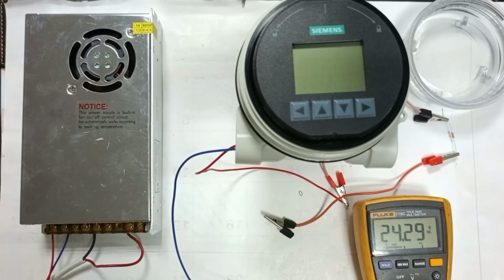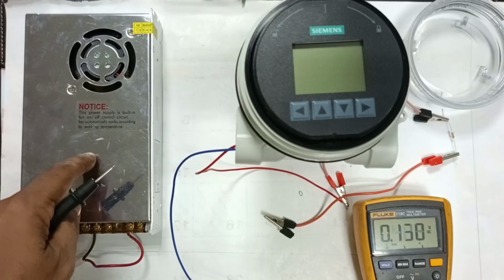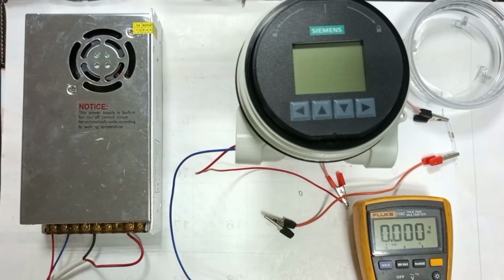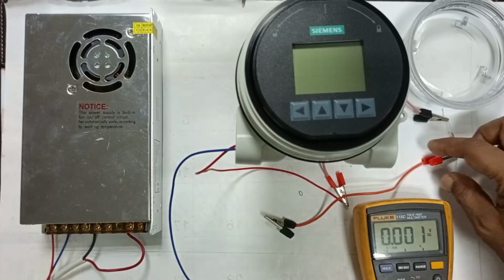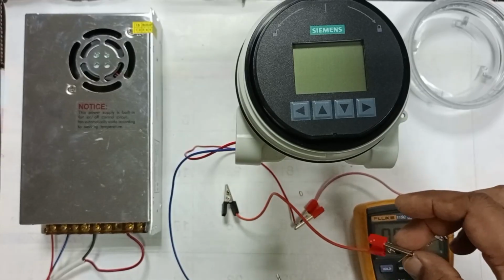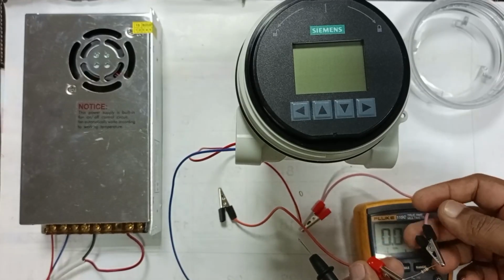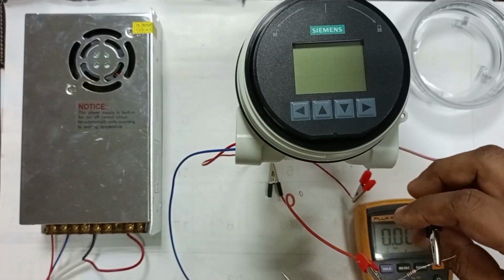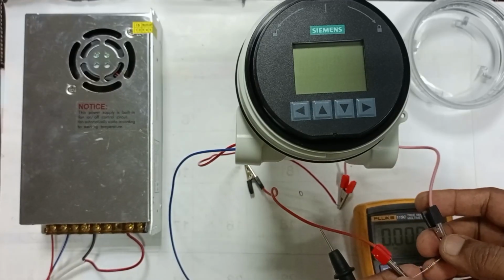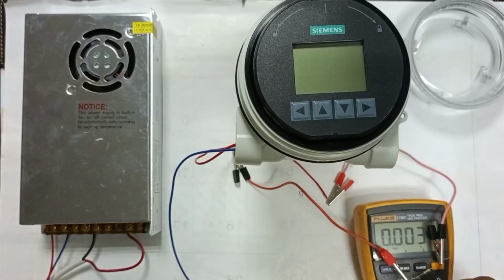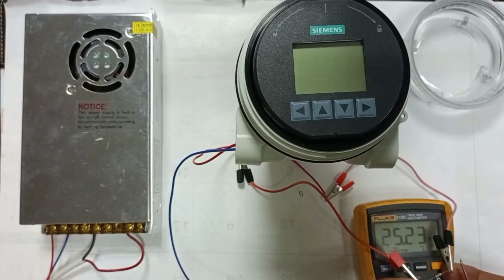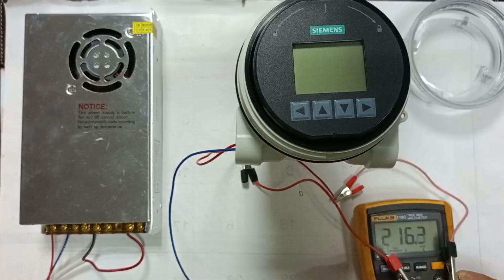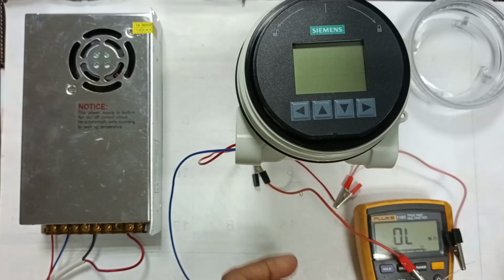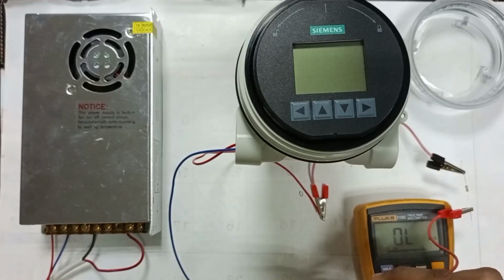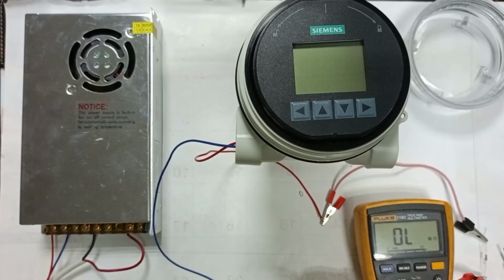Now the transmitter is open and the supply voltage is 24 volt DC. Here is the power supply unit. Its input is 220 volt AC and output is 24 volt DC. Now the transmitter we are using is not connected to the field, so we used here a resistor whose value is 220 ohms. You see its value. If we measure this value, then it will show 216 ohms. So we used this resistor as a series load, and now we will connect the power supply.